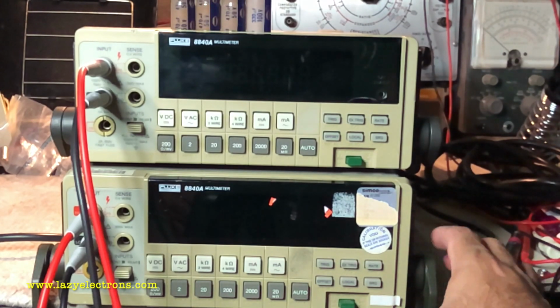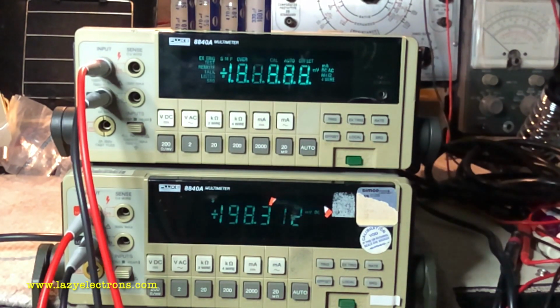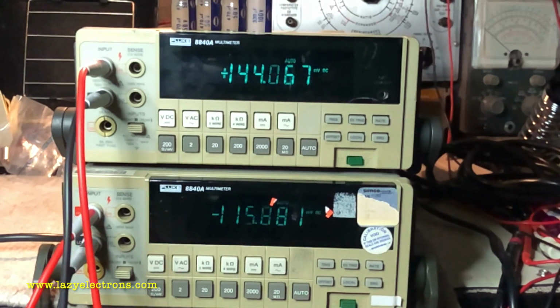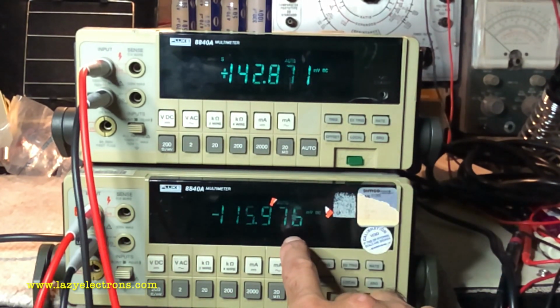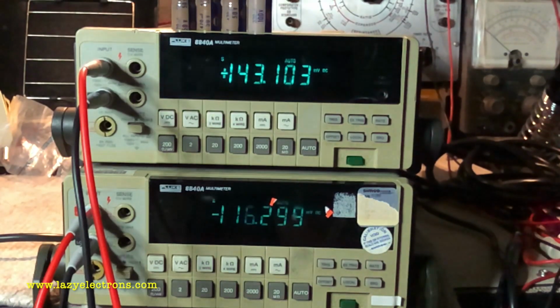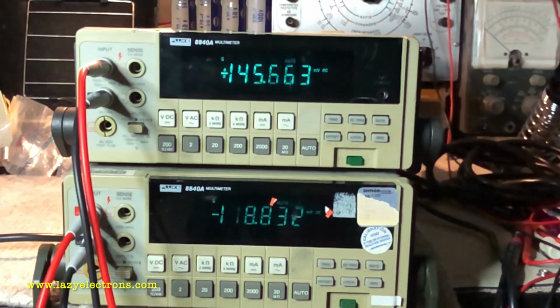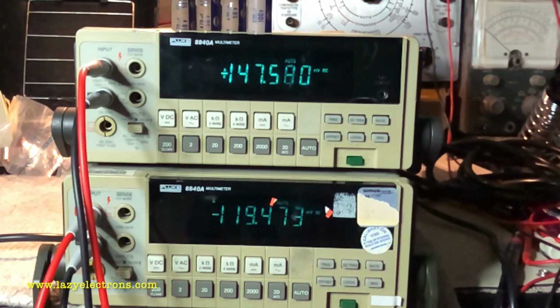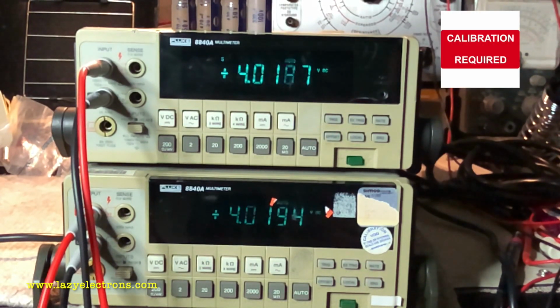Okay, here we go. I have both of them stacked one on top of the other, and both are working. Let's do a measurement in terms of comparison. Before that, a quick point: the meter below looks a little bit dim. That's mainly because of the lighting, but when I look at it, I don't see much of a difference in the VFD brightness. So let's apply a DC voltage and see how these guys compare with each other. 4.0187 and 194. Of course, these guys are not warmed up, so I'm not gonna say they are drifted or whatever. They need at least 30 minutes to 1 hour warm up before they come up to their spec, but they're not drastically off. Now let's try AC.